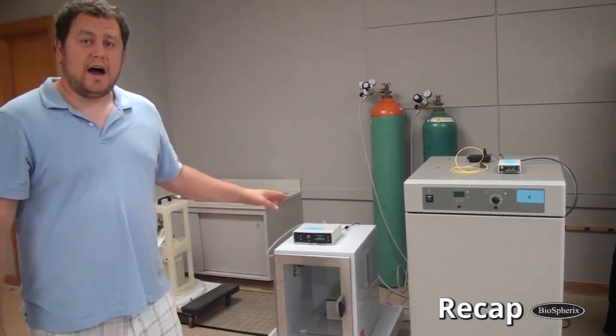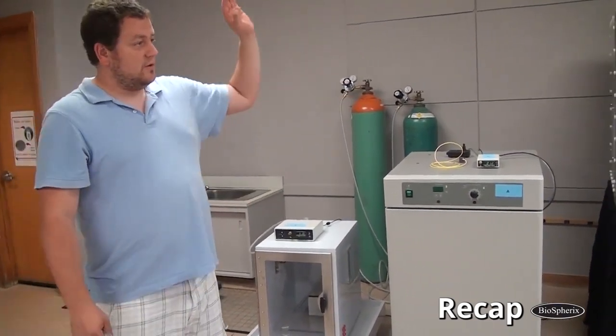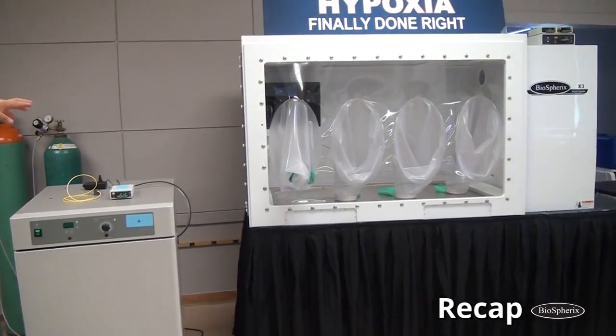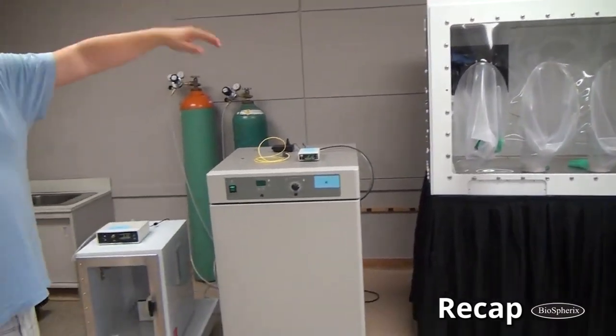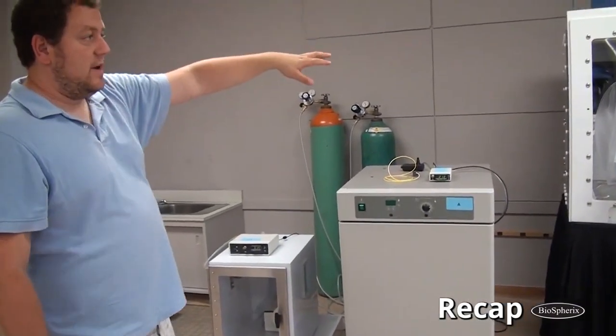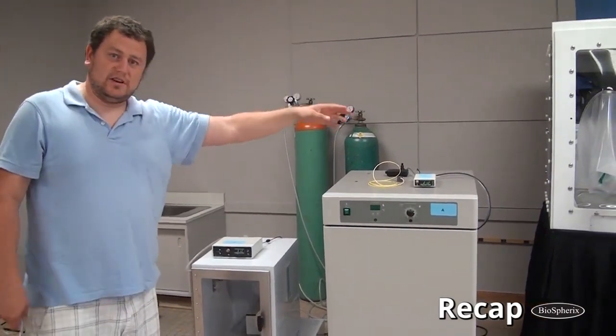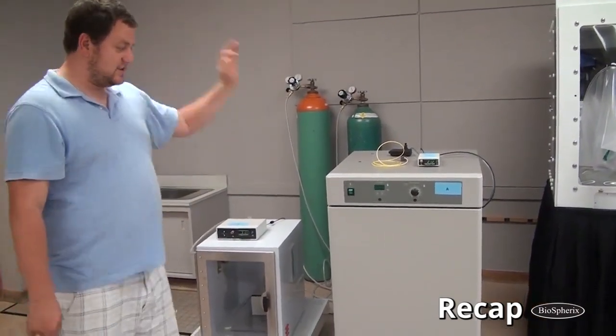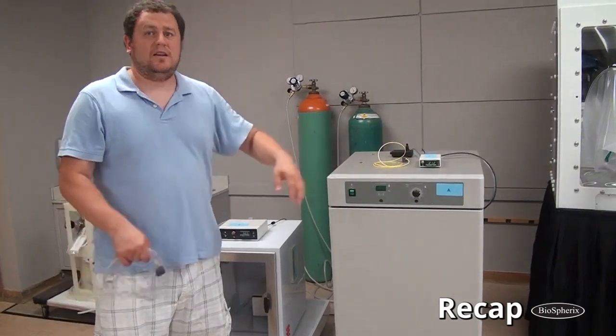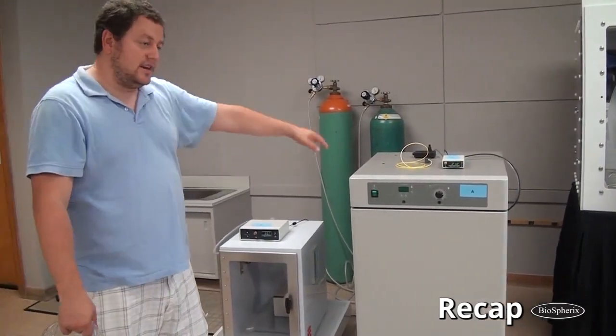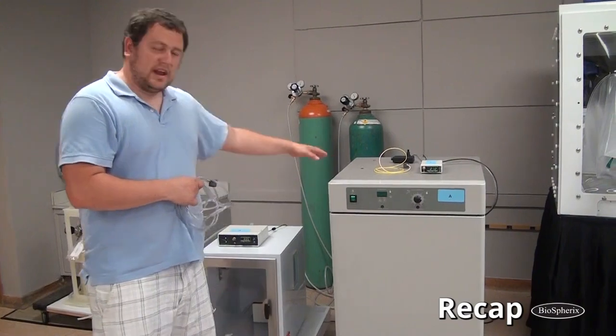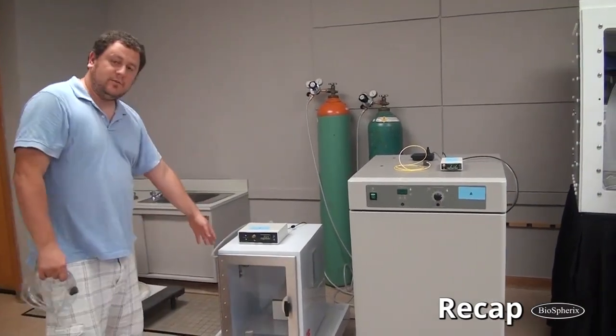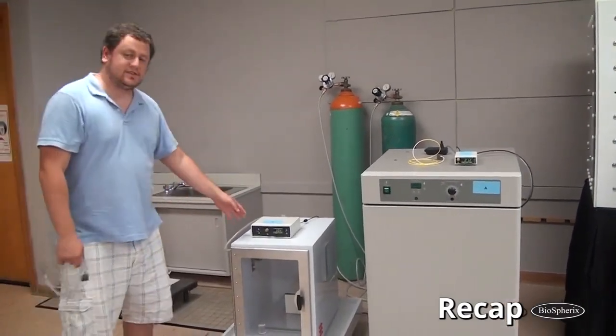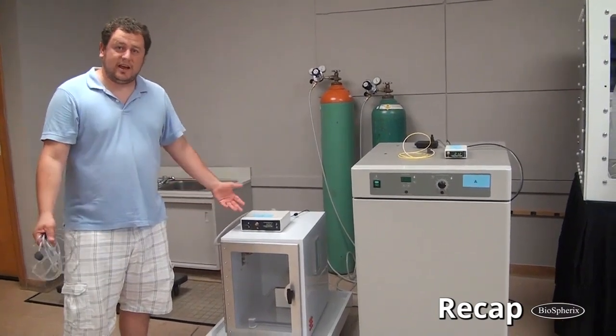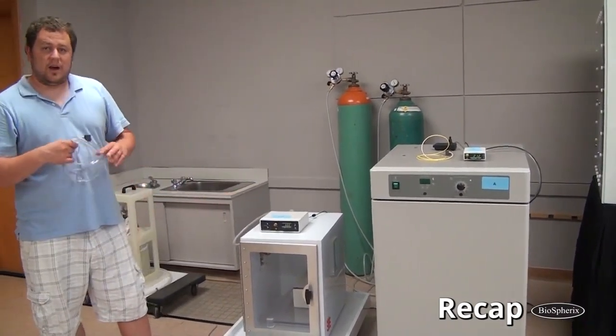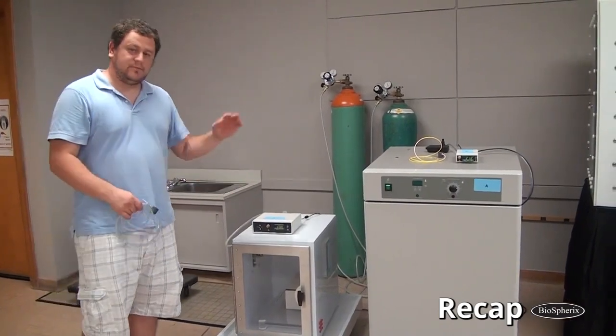Again, it doesn't matter what model setup you have, whether you've got the X3 independent setups, C shuttles, iGloves, any of those glove box setups, calibration is going to be exactly the same, whether you're running a cell system, or the P110, or a P360 on an incubator, same exact calibration, or if you're running an animal setup, or the P110, a P360, a dual redundant fail-safe setup, it's always done exactly the same, just like you saw.